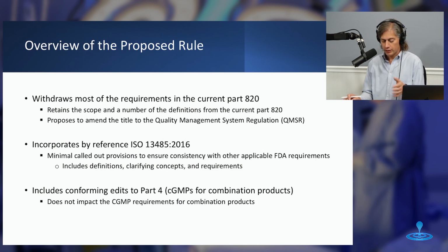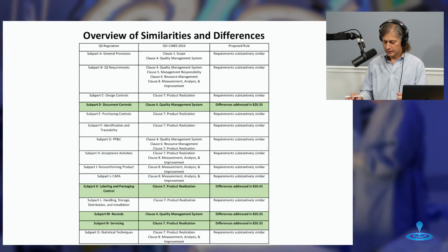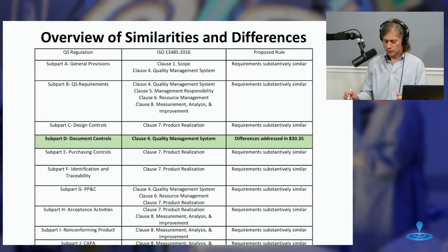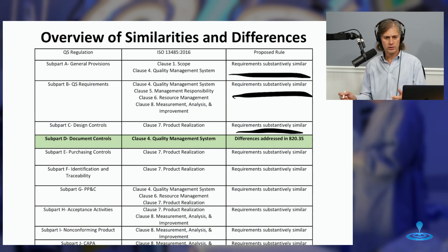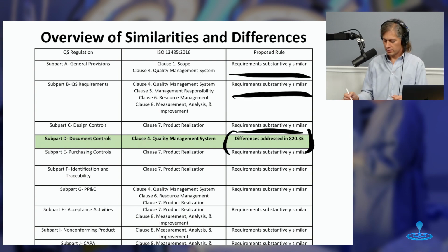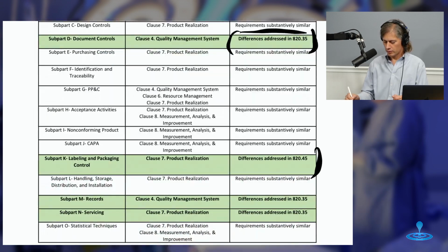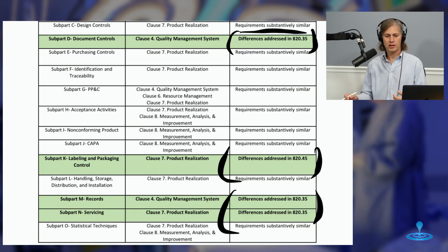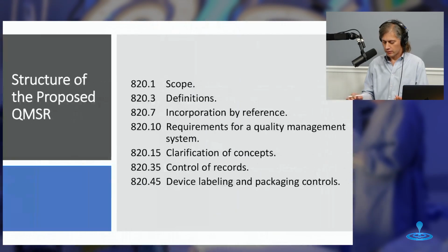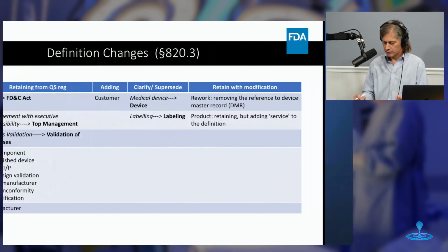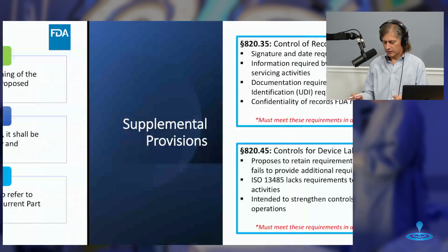So the idea, like we said a minute ago, pull out most of 820, incorporate by reference ISO 13485. And you can see here in this table, well, if the requirements are substantively similar, then couldn't we just use 13485? Or if there are things that we do need to address, we'll have parts of 820 that still exist to be able to reference those. In other words, we'll keep the things in green and address the differences, but the other parts will just reference 13485. And that sounds really good. A lot of cool things in this document.